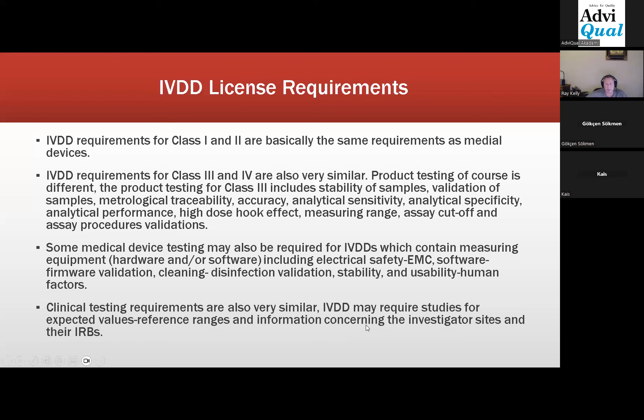License requirements are pretty much the same, use the same forms, very similar dossiers. Some of the testing and the performance of an IVD is different. It's more about accuracy, analytical sensitivity, specificity. So if you're experienced with IVDs, then you know what type of data they're looking for in the dossier versus a normal medical device. And if your medical device includes instruments, whether that be a hardware instrument or a software instrument, then you have the regular medical device stuff: EMC, safety, software validation, cleaning, disinfection, usability, etc. But the bench testing is where there's a difference between medical devices and IVDs when it comes to what you're actually testing, and that's not just for Canada, but that's for the U.S. and probably for Europe, I would think as well. And then your clinical requirements are similar.